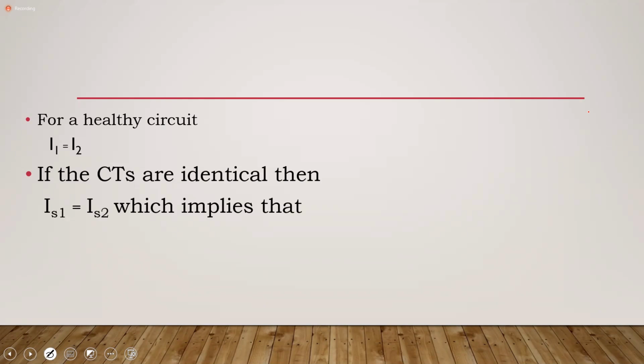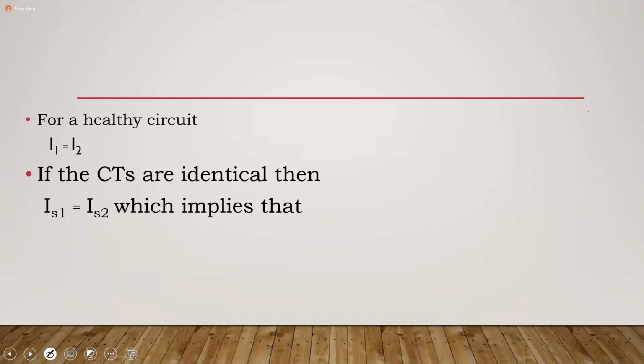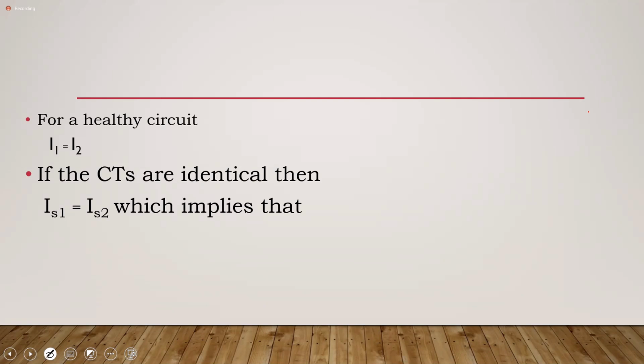Good. So if that is true, then I1 equals I2, which means that for the CTs, IS1 would be equal to IS2. And I suppose the big question in some person's mind is, for the transformer, how do we get IS1 equal to IS2, given that the secondary current will be different in value from the primary current? That would be an excellent question. However, the CTs are connected in such a way that the same current would be seen in terms of the output. So the turns ratio for the transformer is taken into consideration in selecting the turns for your CTs. Okay? All right. And so it means that IR is equal to 0.